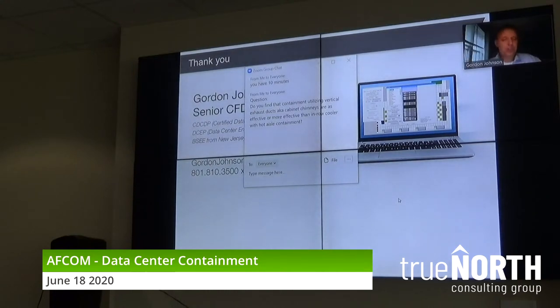So the good news to what you're saying is, the higher the server kW, the less airflow you're going to need compared to what you may have thought a couple of years ago, but you're still going to need containment in order to raise the temperatures. Otherwise, you're still going to be pumping out 55, 60, 65 degree temperatures in the data center. Does that answer your question?